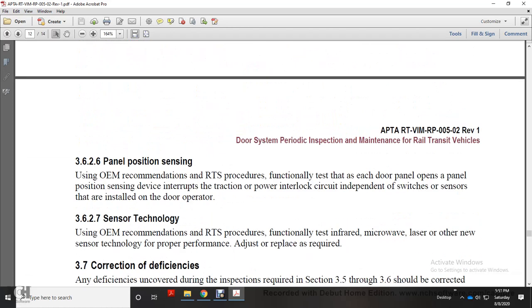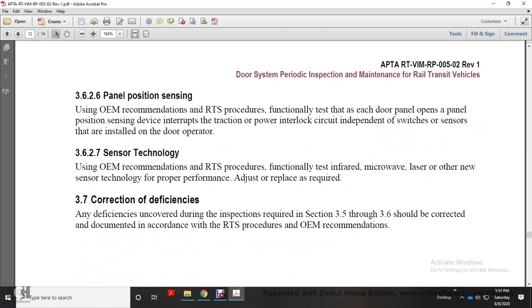Alright, 3626, panel position sensing. Using the original equipment manufacturer recommendation and rail transit system procedure, functionally test each door panel's open and closed position sensing device. Verify the traction power interlock circuit is independent, with the switch or sensor installed with the door operator. 3627, the sensor technology. Using the original equipment manufacturer recommendation and rail transit system procedure, functionally test infrared, microwave, laser, and other new sensor technology. Proper performance; adjust, replace as required.